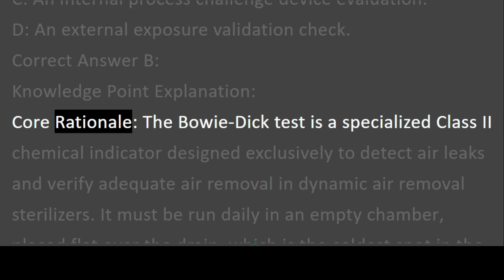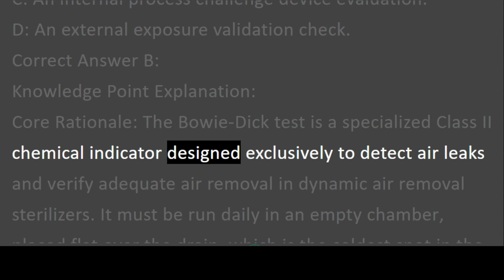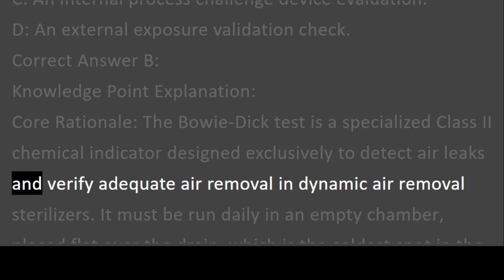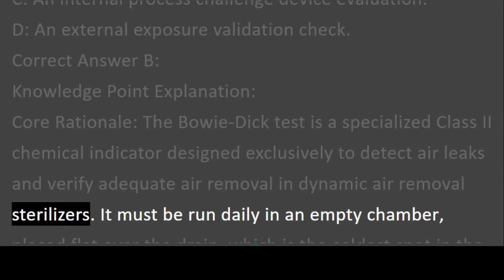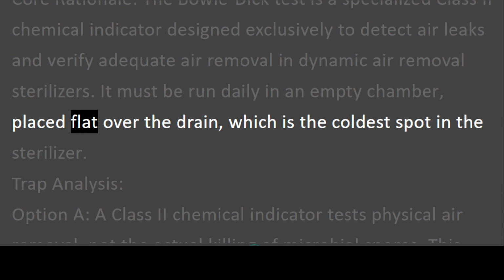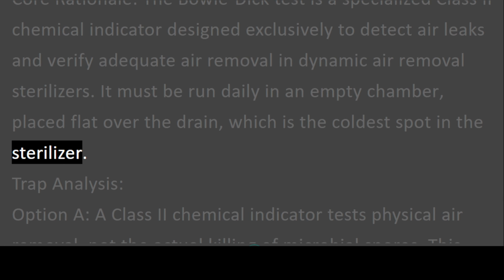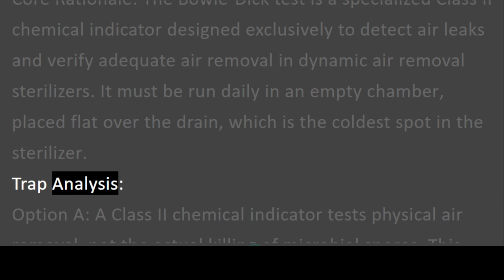Core rationale. The Bowie-Dick test is a specialized Class II chemical indicator designed exclusively to detect air leaks and verify adequate air removal in dynamic air removal sterilizers. It must be run daily in an empty chamber, placed flat over the drain, which is the coldest spot in the sterilizer. Trap analysis. Option A.